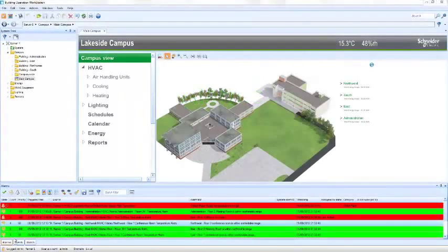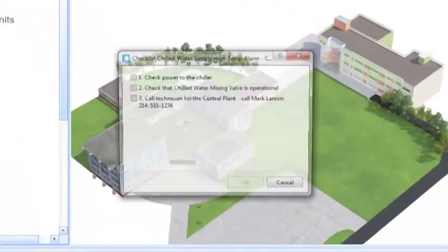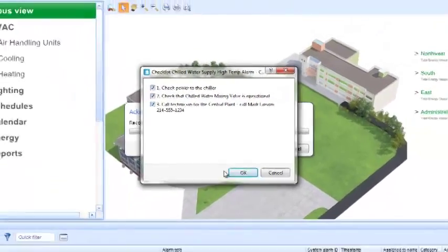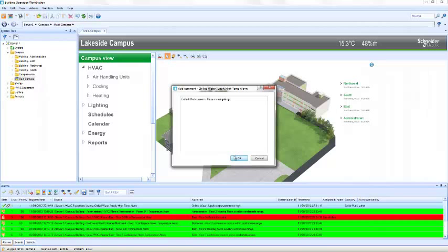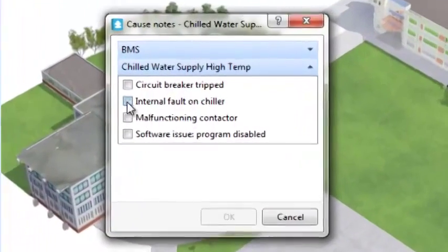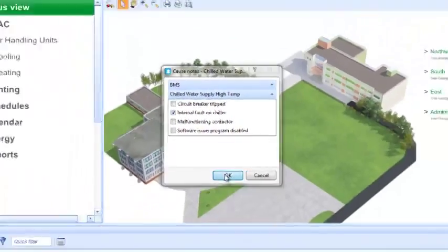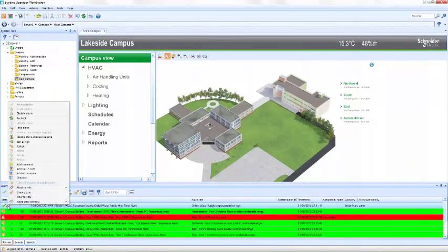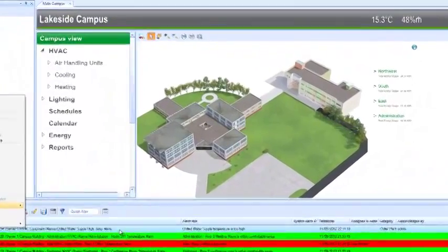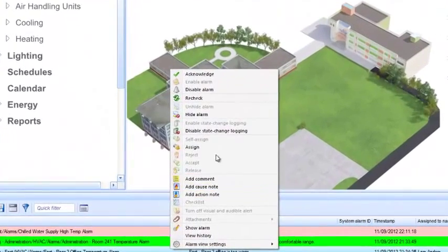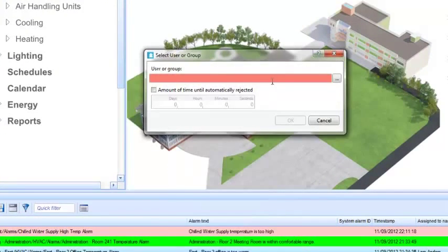When an alarm occurs, StruxureWare Building Operation can require the user to acknowledge the alarm, follow a checklist, make comments, and enter cause notes to ensure that site policy is followed. Documents, graphics, and even videos can be attached to the alarm to provide all the information needed to remediate the problem. Specific alarms can be assigned to individuals via email to ensure the right person is notified.